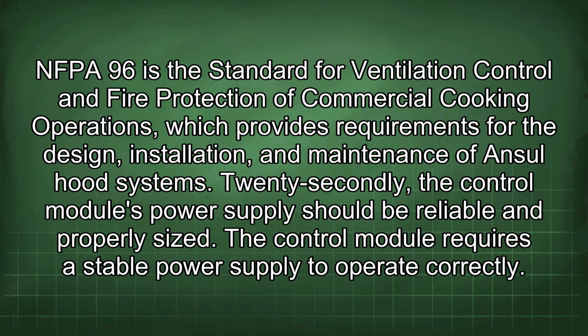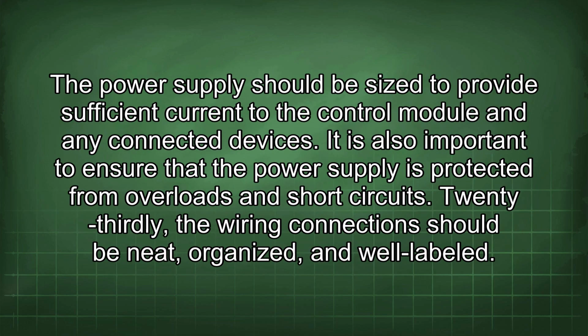Secondly, the control module's power supply should be reliable and properly sized. The control module requires a stable power supply to operate correctly. The power supply should be sized to provide sufficient current to the control module and any connected devices. It is also important to ensure that the power supply is protected from overloads and short circuits.